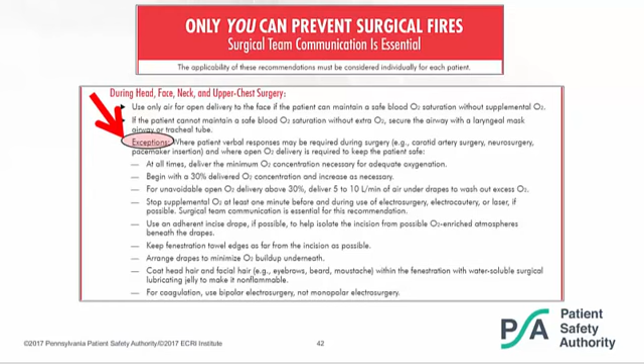At 30% oxygen, you do not have the hazard of a flash oxygen-enriched fire that I demonstrated in the black and white video. At 30%, you do not. So if you can get by with 30%, that's where you would start. And remember, you're also monitoring the patient's pulse oximetry to see whether or not they are desaturating. There are other bullet items there on how to minimize the risk for the exceptional cases. Go through these with your anesthesia staff and with the surgical staff and understand which ones may be best applicable for the exceptional cases. All of this presumes, however, that you've done an assessment for that individual patient and that they are, in fact, an exception where they need to have open oxygen on the face.